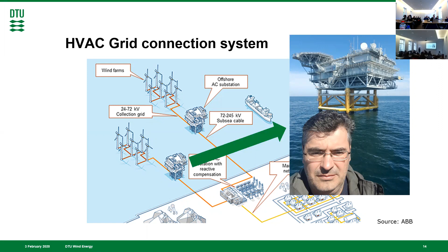Another thing influencing the grid connection of wind farms: this is the single line diagram of an existing wind farm in Denmark, used to be large, now medium to small, only 400 megawatts. You'll see the same wind turbines, transformers, common bus, but when it hits the landfall there's a STATCOM, and since it also has a land cable transmission before connecting to the main grid, it actually has four STATCOMs.